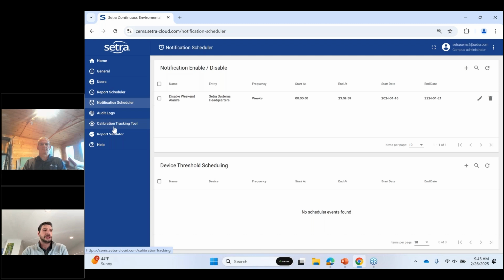We also have a calibration tracking tool built into the software, so the system will send you notifications 30, 60, 90 days out when your devices are approaching recalibration. You can think about either sending the equipment back to Setra or having a third-party company come on site to do the calibration. We just partnered with a company named Standard Calibrations that can field calibrate all of our sensors with the exception of our particle counters, that's the only thing that would have to come back to Setra for recal.